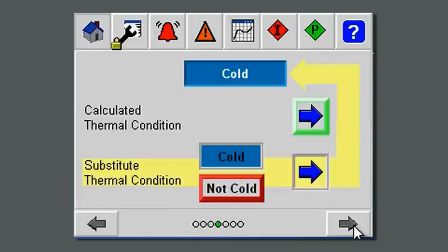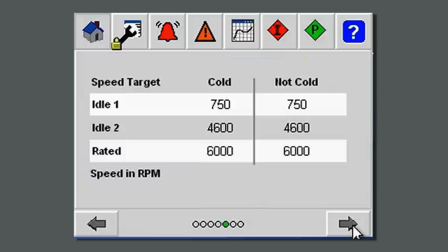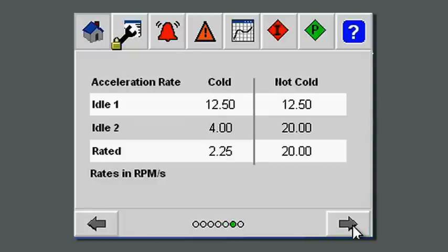The startup sequence can be configured for a cold or a warm start. It'll also let you bypass and substitute a thermal condition if you're doing a restart and you don't want to wait for a long thermal warm-up cycle. The speed target for cold and warm starts gives you an idea of where the particular idle speeds are within your startup sequence, and in the next screen you'll see how long you'll spend in each of those particular zones.